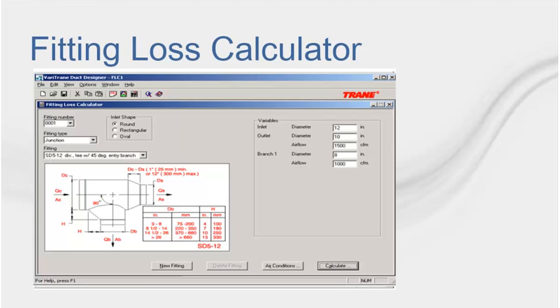The Fitting Loss Calculator computes the total pressure drop of a fitting based on its configuration, dimensions, and the airflow passing through it. The calculations are based on an extensive library of fittings originating from the United McGill and ASHRAE 1993 duct fitting database.